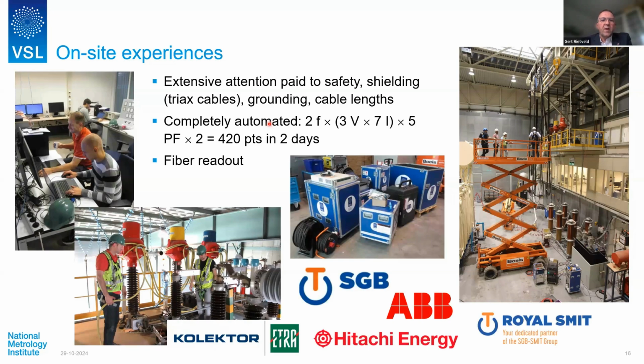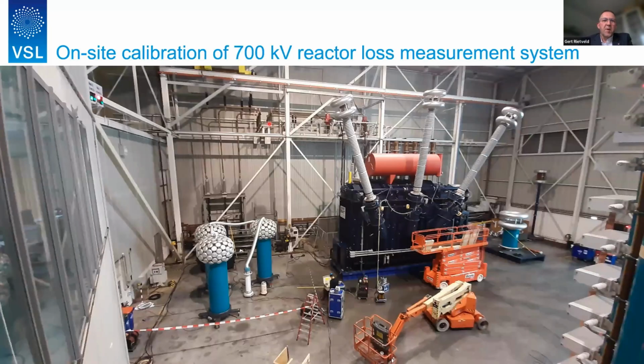This is the EU industry that we have been servicing with our measurement capabilities. And one particular example I would like to show, that I'm particularly proud of, and I see that one of the colleagues where I've been doing the calibration is online. This is the calibration on site of a 700 kilovolt reactor measurement system. And here you can see my former colleague. He is a 2-meter tall guy. This rack is about 1.7 meters. So again, you see an indication of the huge instrumentation. Just the measurement instrumentation: these are 700 kilovolt high voltage capacitors, a 200 kilovolt reference, and our generator up to 150 kV. The actual current circuit is located here, and here is our current generation circuit.